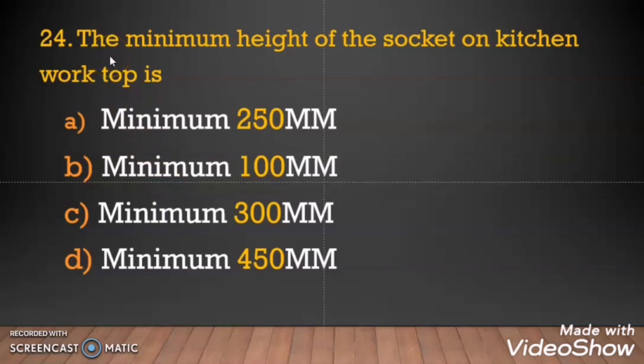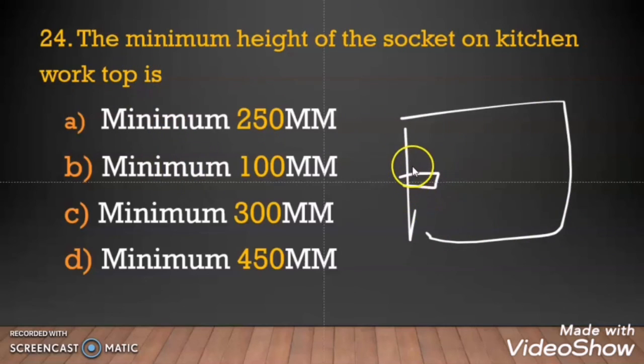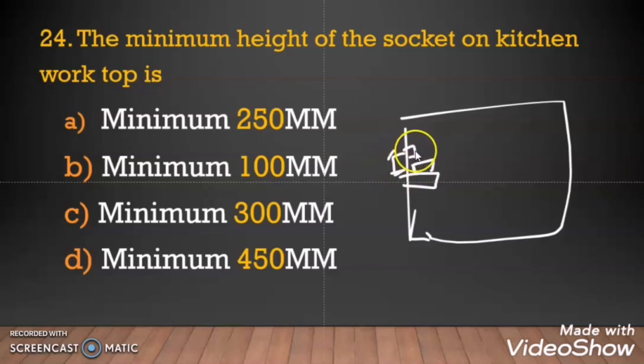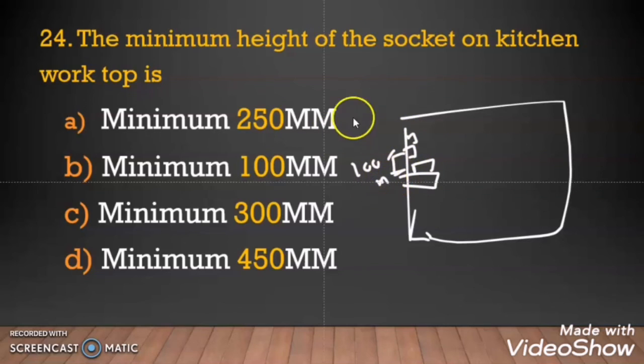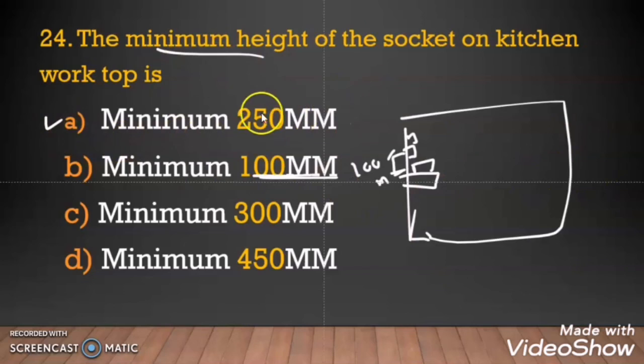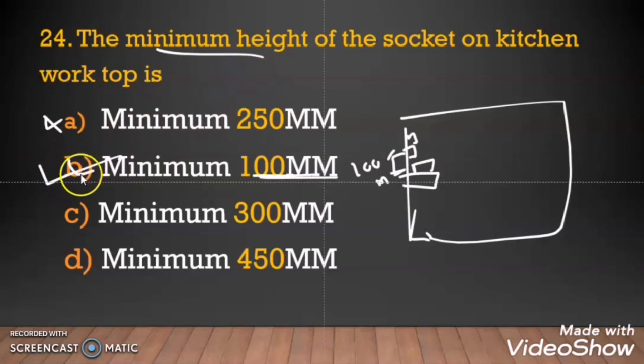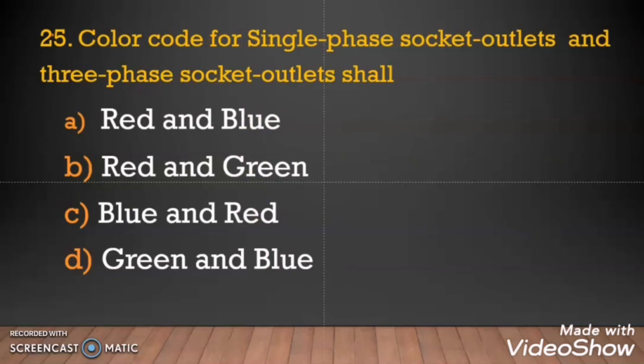Question 24: The minimum height of the socket on the kitchen worktop. In a kitchen, there is a worktop where we keep stoves, microwaves, cookers, and other kitchen equipment with sockets nearby. As per ADDC regulation, the minimum height is 100 mm from the worktop. It can go up to 250 mm, but the minimum is 100 mm. For DEWA regulation the minimum would be 250 mm, but as per ADDC regulation, option B, 100 mm, is correct.